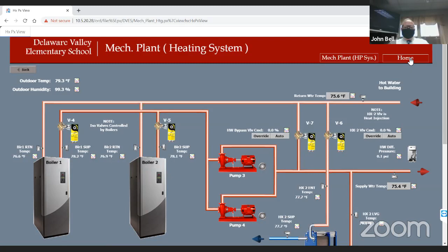So we regularly deal with complaints about coldness in the winter by adding to the existing system. In the 9-10 building, for example, when the kids come from the high school across the sidewalk and through the 9-10 entrance, it gets very cold there in the wintertime, so we had to put an infrared ceiling mounted heater there. The new CTE wing, where they come out down by engineering, they keep those doors open for the kids and it gets cold quick, so we had to put a heater in that doorway. So even though we have design systems, we supplement to deal with our particular situation because we operate differently than the engineers think we're going to operate.